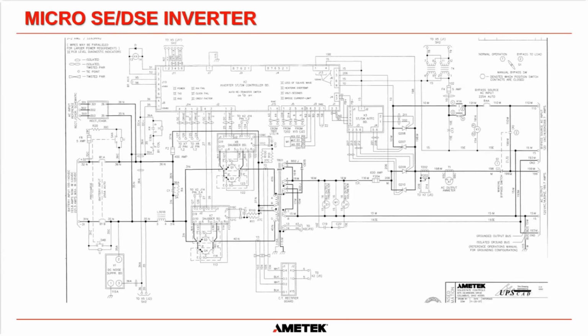On the ferroresonance system, what the ferroresonant transformer does is use a tank capacitor, which is there, and some inductive reactance in all of these windings here. What a ferroresonant transformer does is it creates a constant voltage transformer. What we do is we actually saturate the core of this transformer using this capacitor here, so that for a certain amount of voltage going in, basically we can probably say you could have anywhere between 100 and 140 volts going into this transformer, the output is going to be exactly 120 volts due to the nature of that transformer.